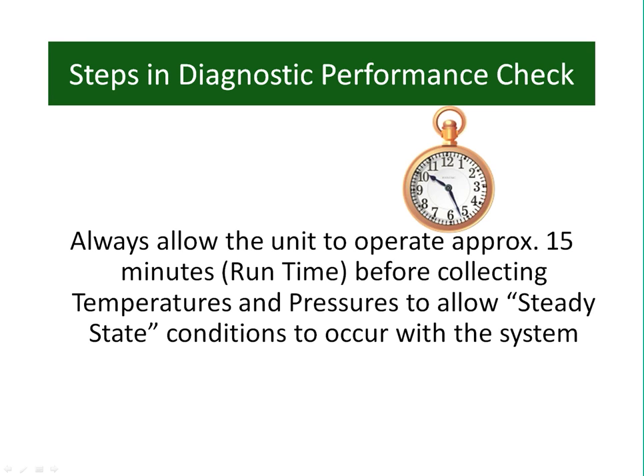And as a reminder, if it is a 2-speed heat pump, it always needs to be in high speed. Why? You need that thing running full tilt boogie. Heating or cooling, whichever mode you wish, always disable the hot water generator. You do not want that influence applied here.